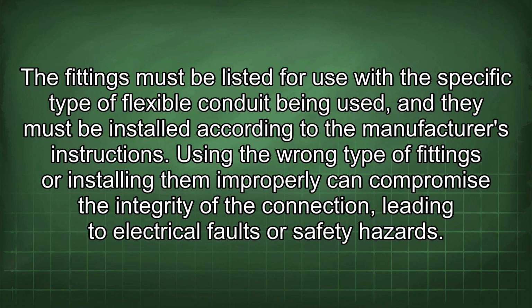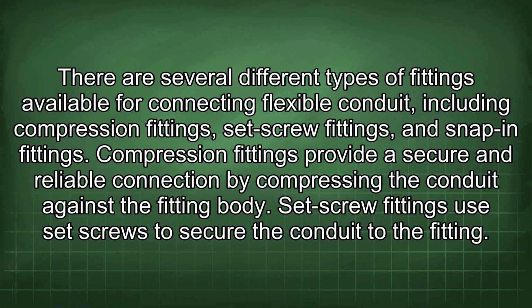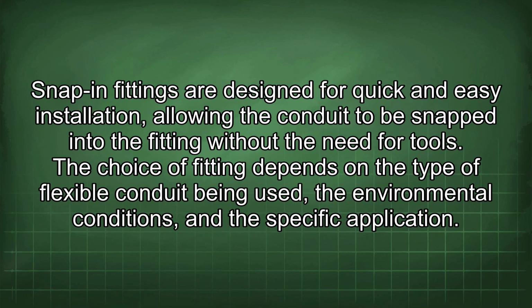Using the wrong type of fittings or installing them improperly can compromise the integrity of the connection, leading to electrical faults or safety hazards. There are several different types of fittings available for connecting flexible conduit, including compression fittings, set screw fittings, and snap-in fittings. Compression fittings provide a secure and reliable connection by compressing the conduit against the fitting body. Set screw fittings use set screws to secure the conduit to the fitting. Snap-in fittings are designed for quick and easy installation, allowing the conduit to be snapped into the fitting without the need for tools.